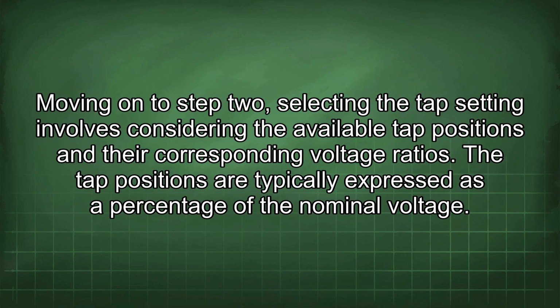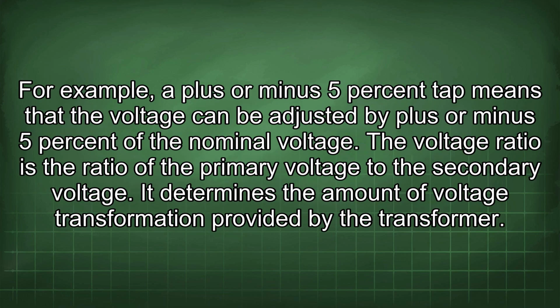conditions. Moving on to step 2, selecting the tap setting involves considering the available tap positions and their corresponding voltage ratios. The tap positions are typically expressed as a percentage of the nominal voltage. For example, a plus or minus 5% tap means that the voltage can be adjusted by plus or minus 5% of the nominal voltage. The voltage ratio is the ratio of the primary voltage to the secondary voltage. It determines the amount of voltage transformation provided by the transformer.